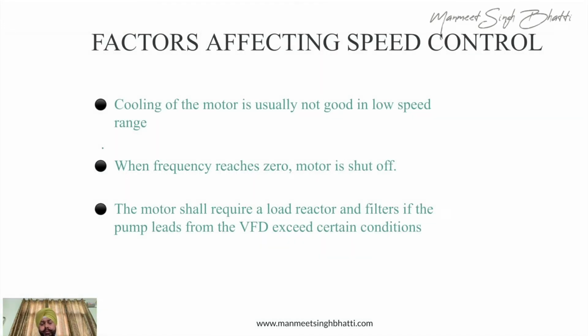Now these are a few of the effects you have to take into consideration when using a VFD. Because the VFD is basically a one way controlling system, because it is going to give the power to that motor. But you must have seen mechanically that motors also have their self-cooling mechanism. There is a small fan on the backside of the motor. That fan is cooling the motor, because motors also get heated up. So if you reduce the speed, the efficiency of that fan also goes down.